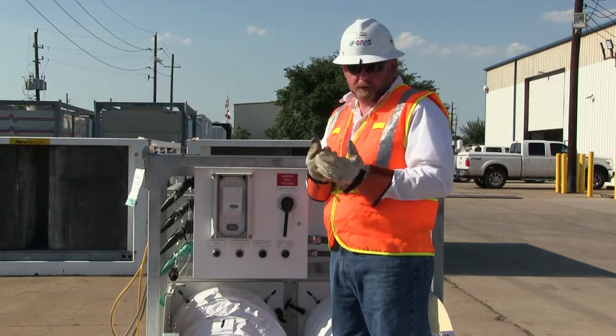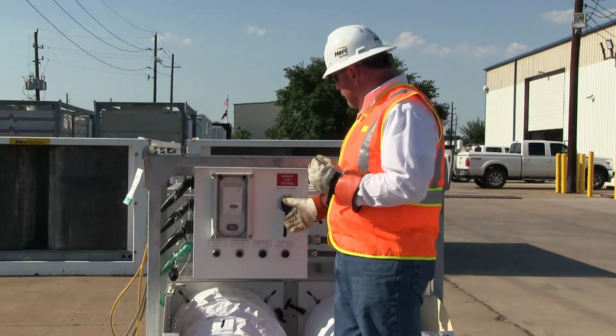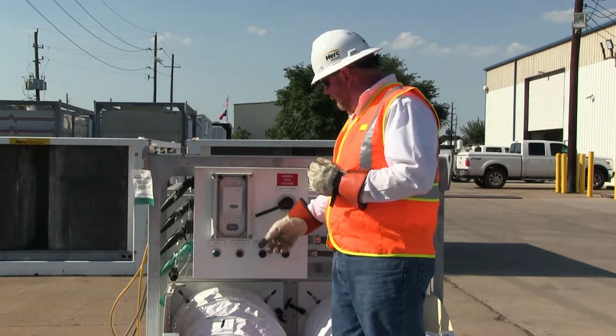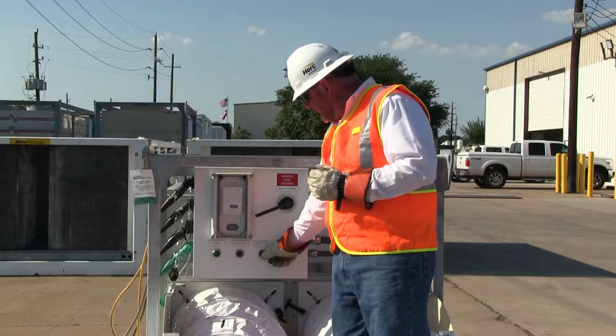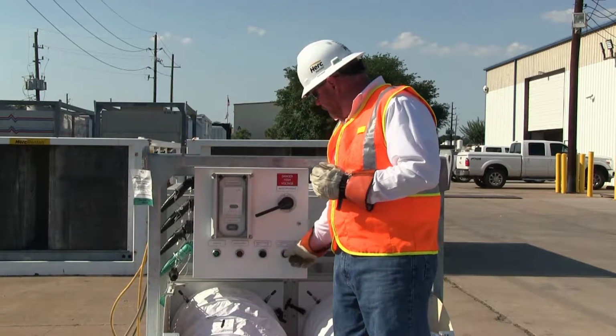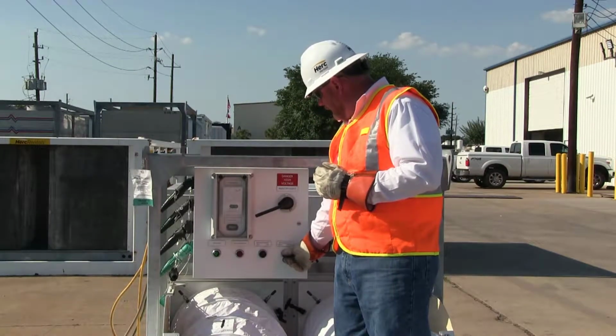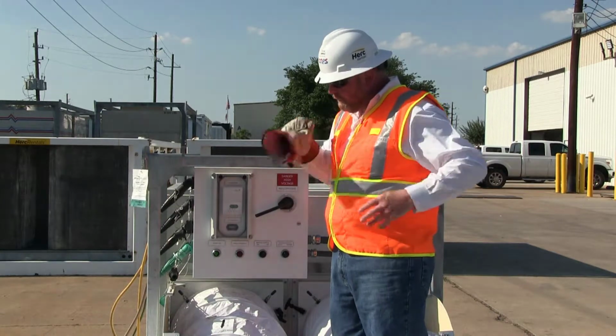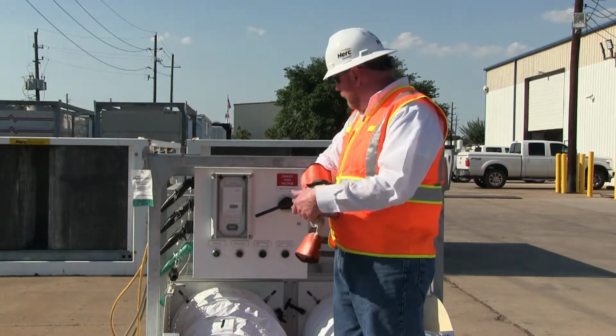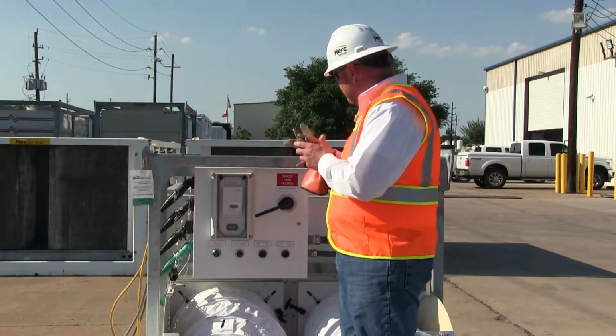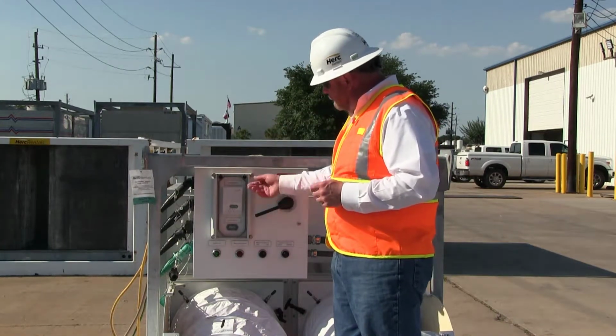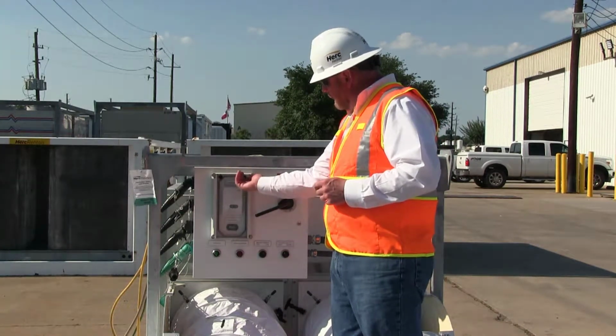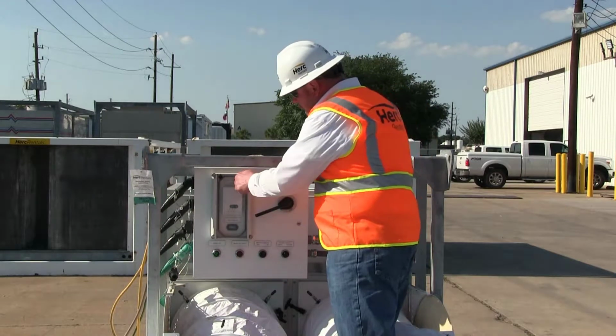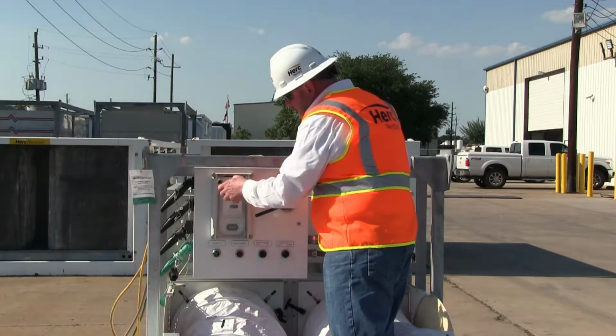So the next step is to start the machine up. We're going to do that by closing the main circuit breaker. Our power light comes on. We're going to turn the master switch on. We're going to leave the system switch in automatic. Now that we're complete with all the high voltage and sharp edges, we can remove our safety hot gloves here. And it takes about 2 minutes for the machine processor to go through a self-test mode. We're going to open up the weather tight cover that's over the thermostat.